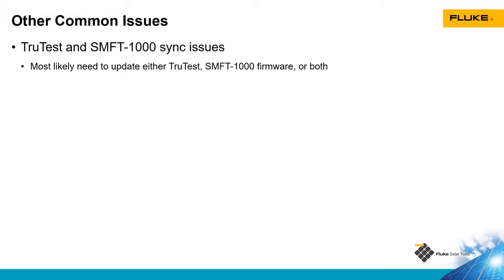Sometimes we run into sync issues with TrueTest and the SMFT-1000. In most cases when that's a problem, either the TrueTest software needs to be updated or the firmware on the SMFT-1000 needs to be updated — sometimes it's both. So if you're having a problem syncing data between the hardware and the software, look for updates and make sure you have the most recent versions.